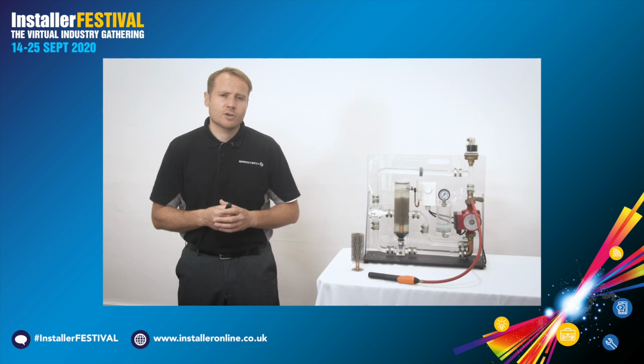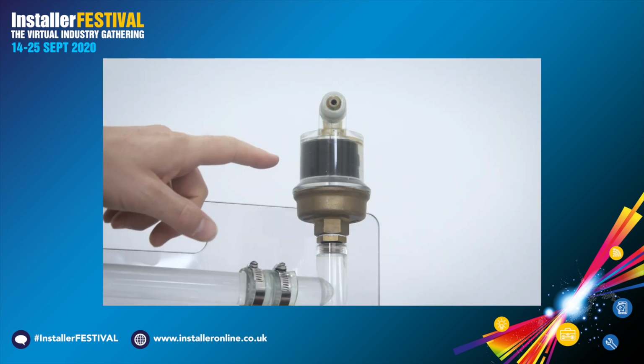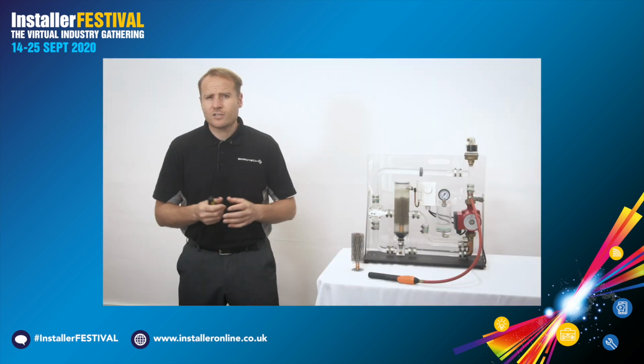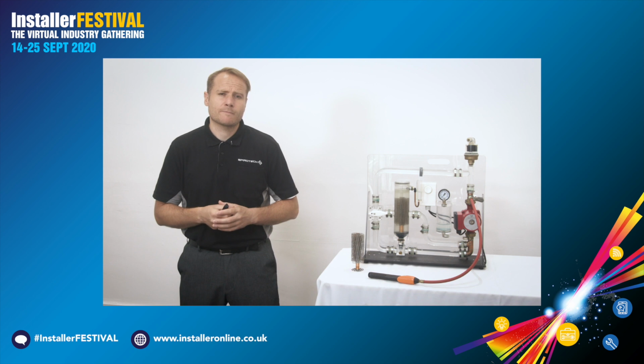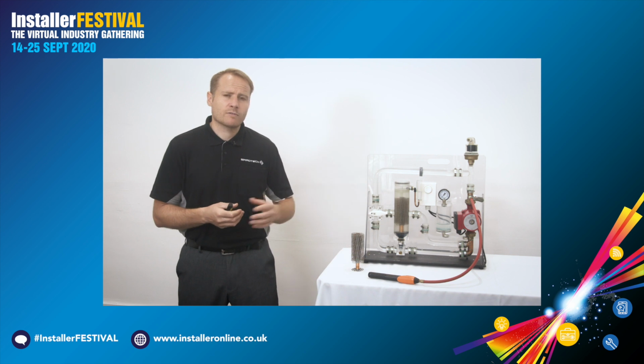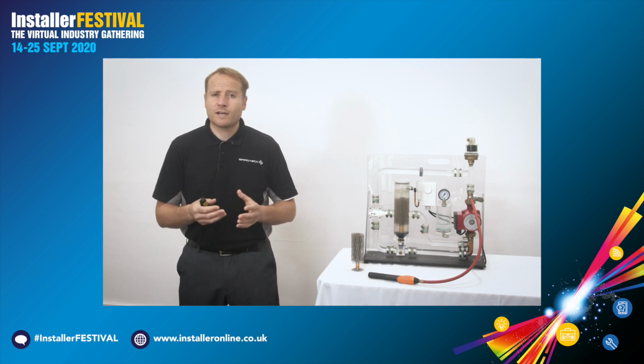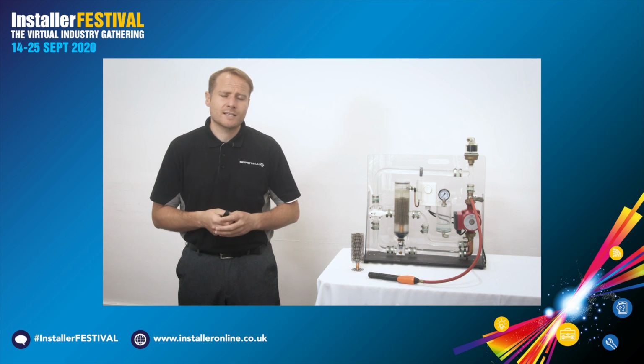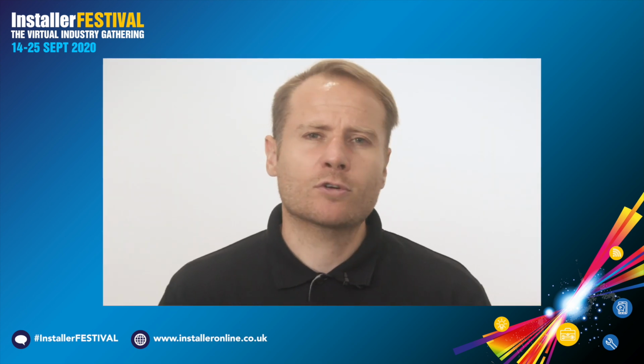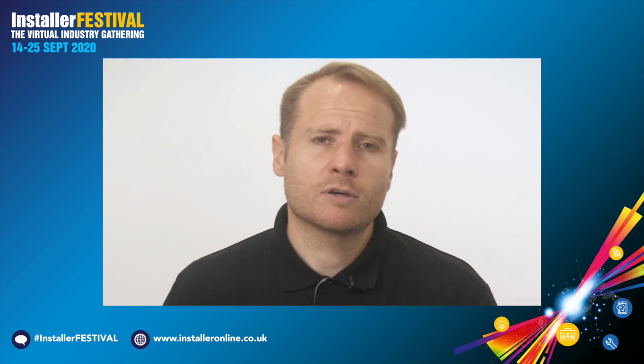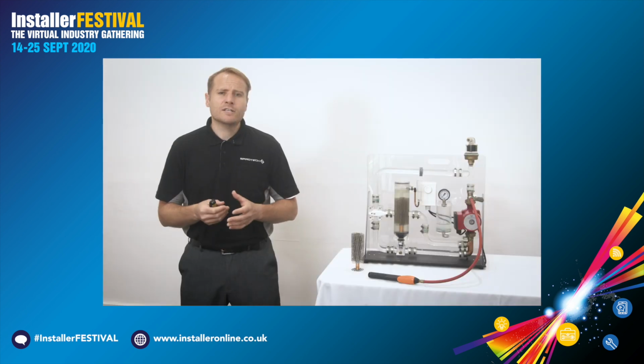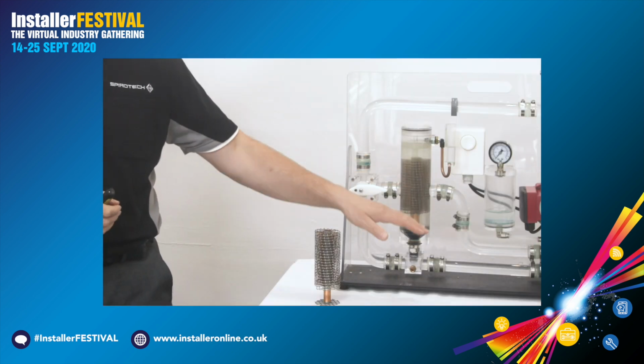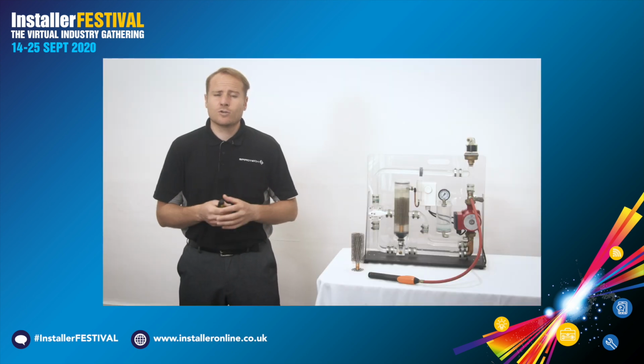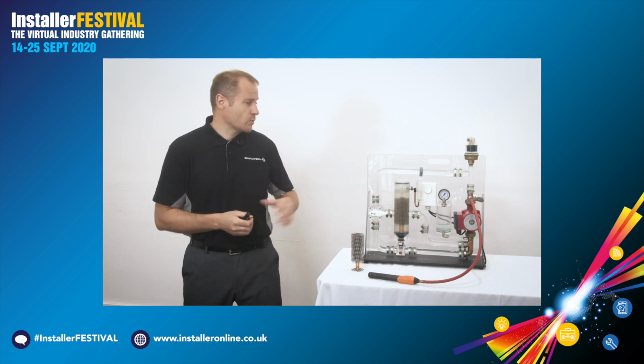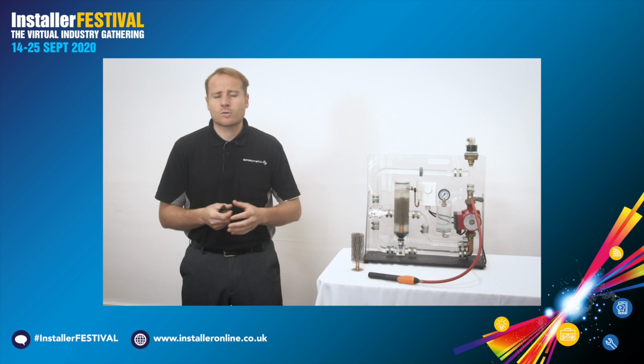One thing I would like to mention though is the AAV, the automatic air vent. AAVs are near enough redundant when there is movement of water. It's not that this isn't a high quality AAV, it is. This replicates one of our own AAVs. And it's manufactured to a very high quality, which is why it comes with a 20-year guarantee. But the application is not to remove free air or microbubbles from system flow. AAVs are used to remove free air when we are filling up a system. And of course they are used to allow air to be drawn into the system when we are draining down the system to release the water.